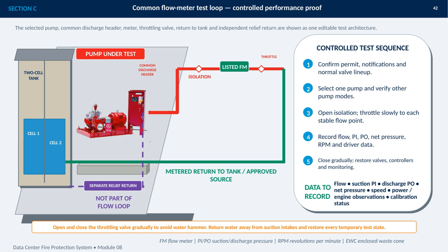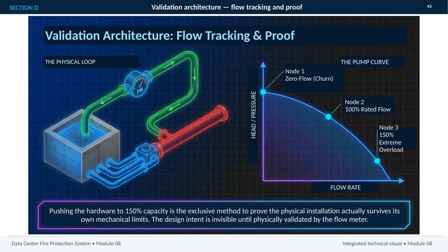Gradual valve movement is essential to limit water hammer, and discharge water must be kept away from pump suction intakes. This slide shows how the validation architecture connects measured flow to physical proof.